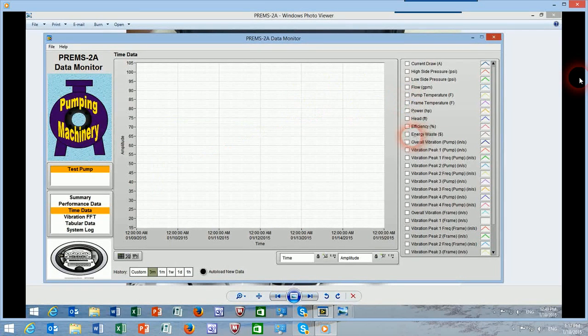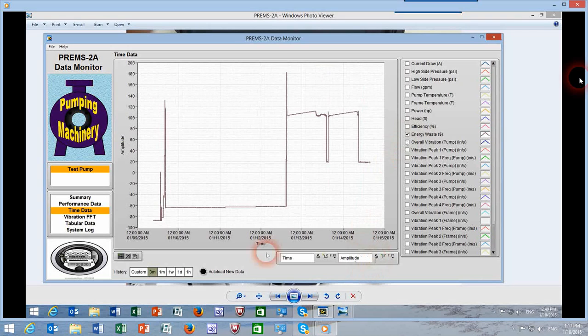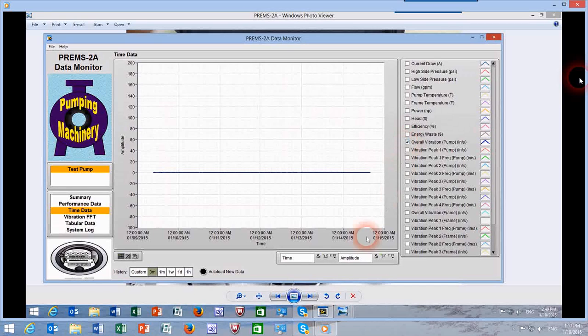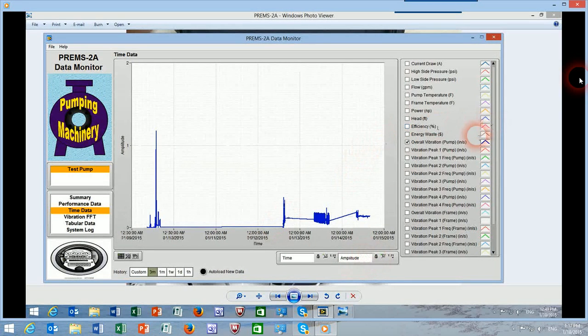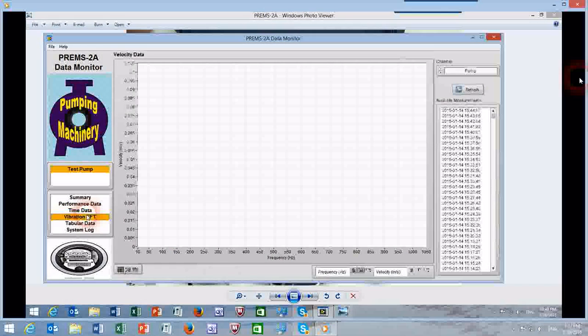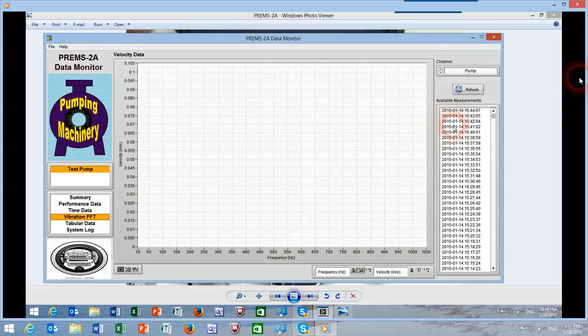Now what happens to the energy wasted? The energy variable, of course, also reflects the operation of the pump. Vibrations, overall vibrations kept changing, quite high, over 1.2 inch per second, and then to nothing, meaning the pump perhaps wasn't running during this time, and then vibration continues this trend. So all the variables can very easily be plotted and downloaded to a spreadsheet or seen on your scatter plot or directly on the screen.